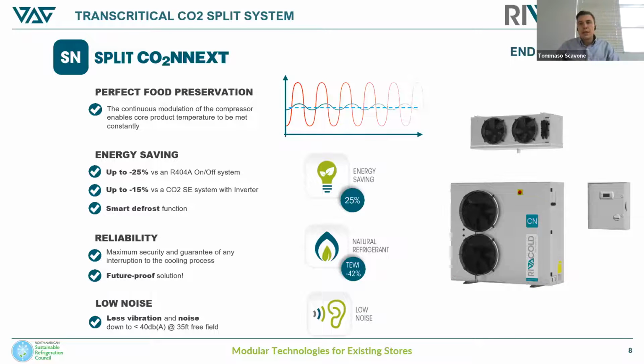On this slide, we're highlighting the main advantages from the end user side. The range fits BLDC compressors driven by inverter. They bring to a continuous modulation of the capacity from 25 to 100% modulation, avoiding those dangerous peaks of temperature that you have with an on-off system. This allows a perfect food preservation, so better quality of the food itself, and also much less food waste.